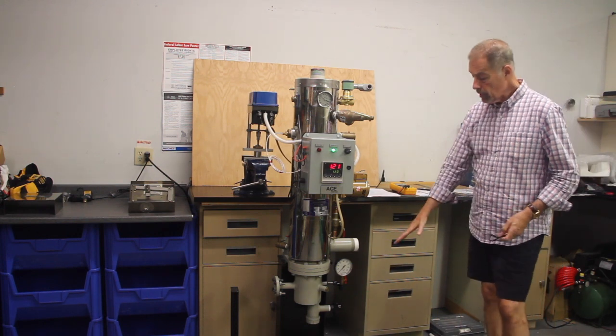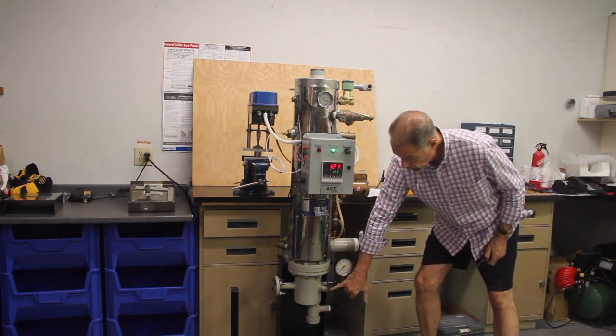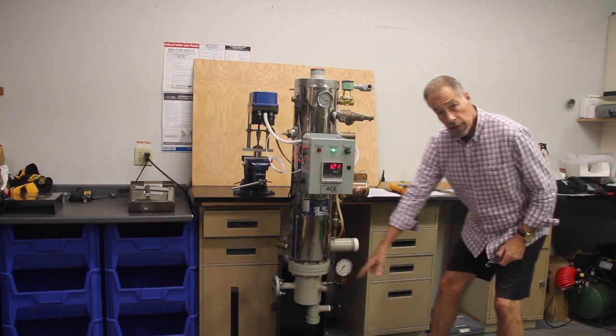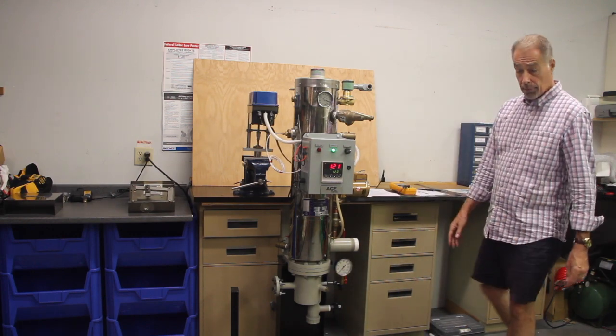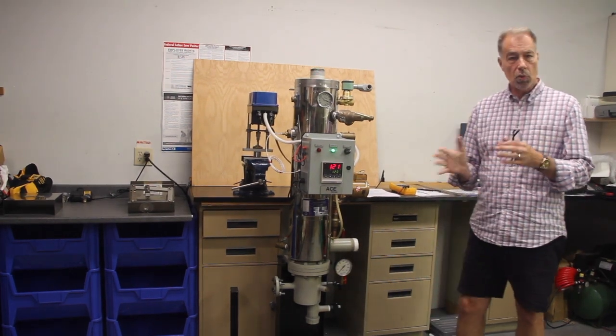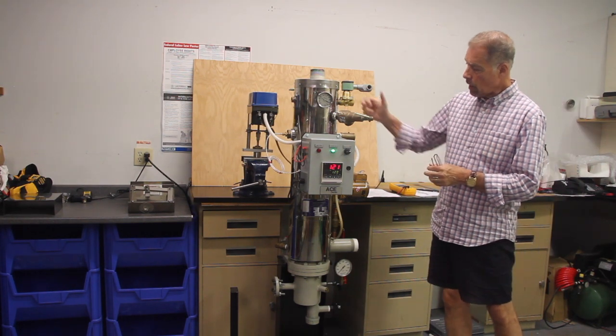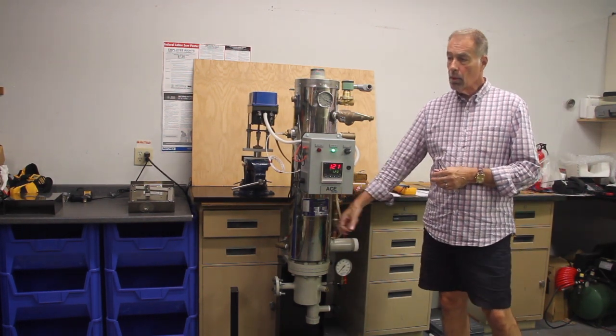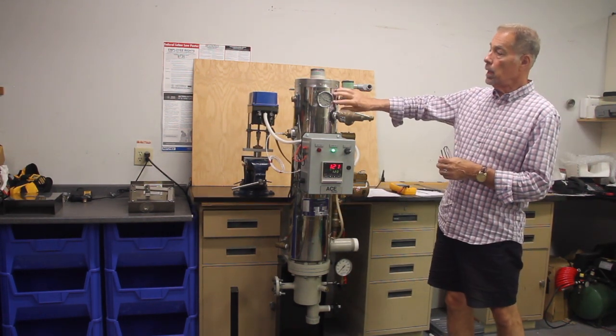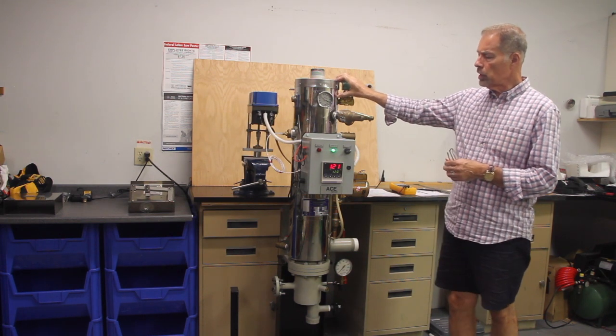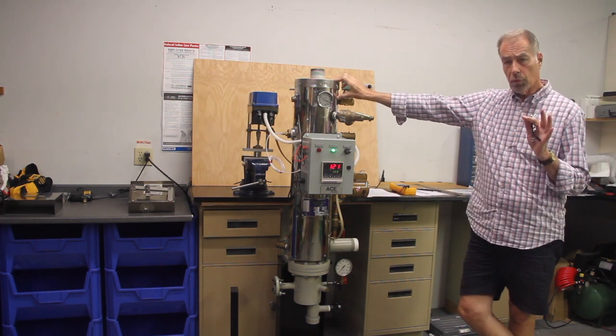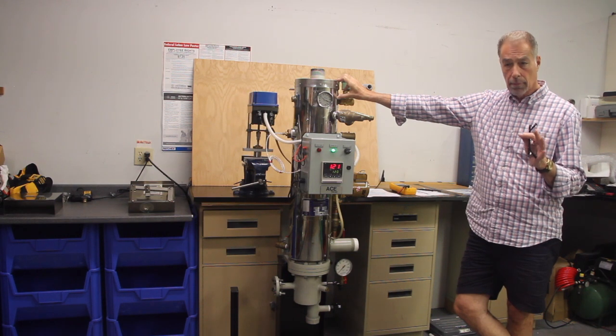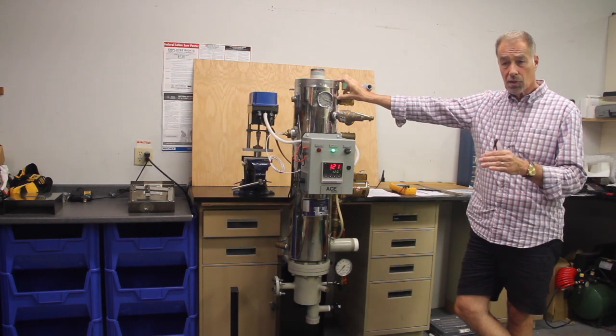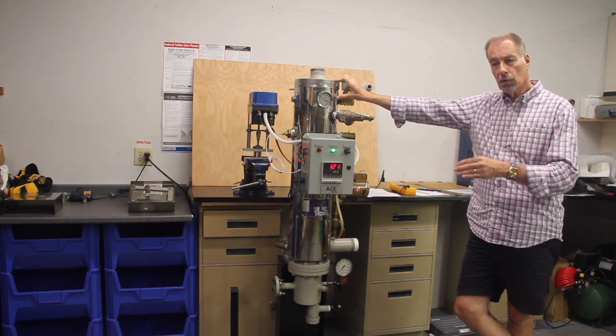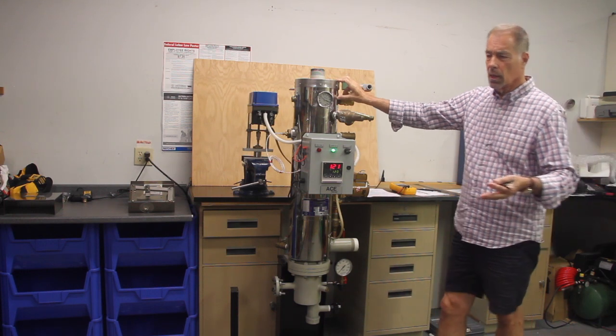We want to have a good pinch. There's a vacuum breaker here that allows that condensate to flow out of the heater. Okay, so to a subcooled device. So the shell of this unit under this insulation, and there's 1.5 inch of insulation here, is 316L stainless. It's passivated, so it'll stand up well to certain chlorides that are in the system.